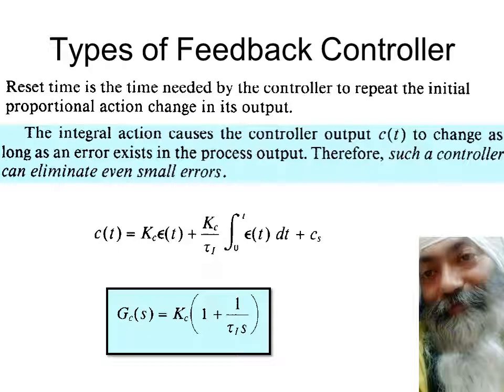And this integral windup is not something healthy. We have to have some mechanism, a limit on this integral thing. We honor it, but the moment the output becomes 100%, this integral should stop increasing, so that by the time the error becomes negative, in the opposite direction, it should start decreasing right from 100 and not from 150. So these are the ways we have to see to prevent this integral windup, to make sure that the output of the controller doesn't become more than 100.